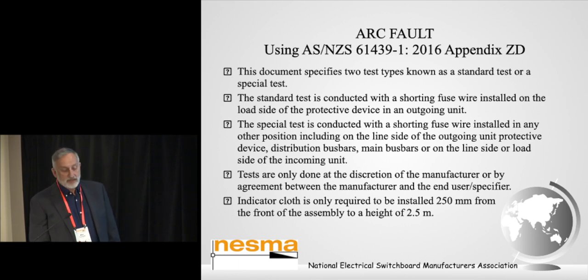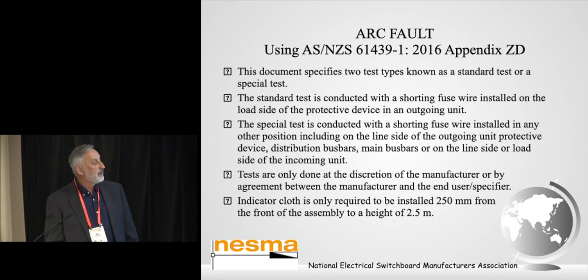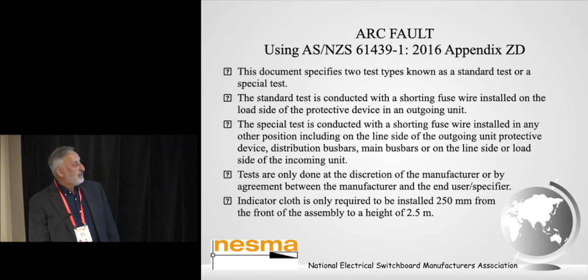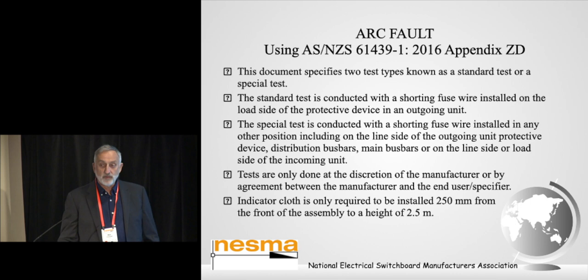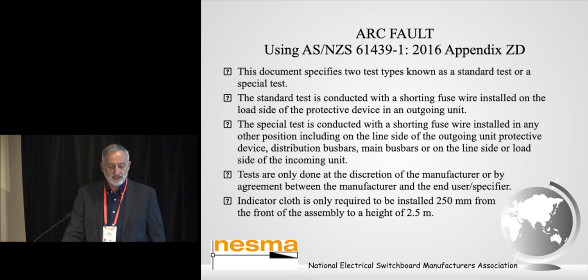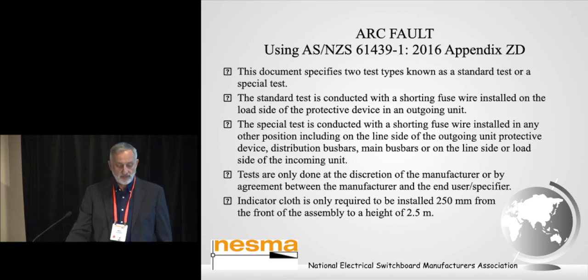So using the Appendix ZD to determine an arc fault performance of an assembly, this document specifies two types of tests, one known as a standard test and one as a special. The standard test is conducted with a shorting fuse wire installed on the load side of the protective device inside a functional unit. The special test is conducted with a shorting fuse wire installed in any other position, including the line side of outgoing units, protective device, distribution bars, main bars, or on the line side or load side of the incoming unit.